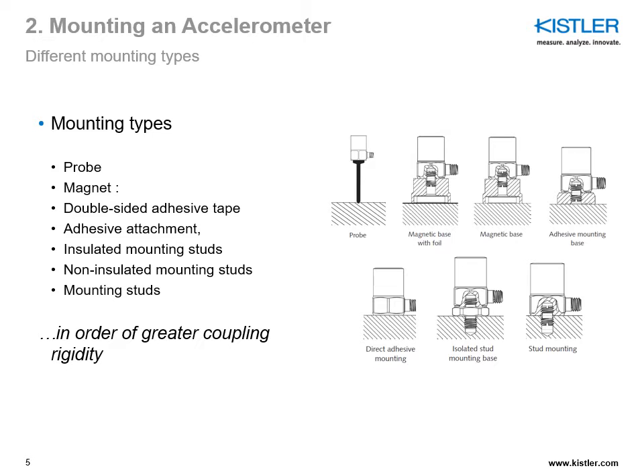Now that we've seen the influence of the sensor mass itself, we're going to look at how to mount a sensor as best as possible to avoid any major influence on the measurement you're performing. You need to be aware that depending on the mounting type you're going to use, you're going to lose in frequency response.